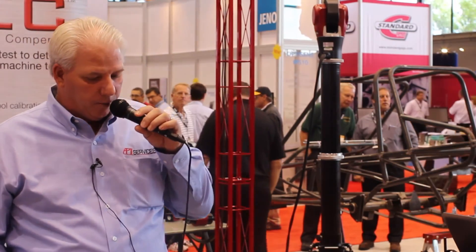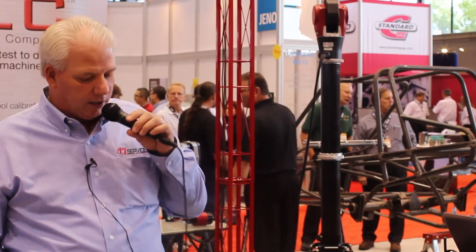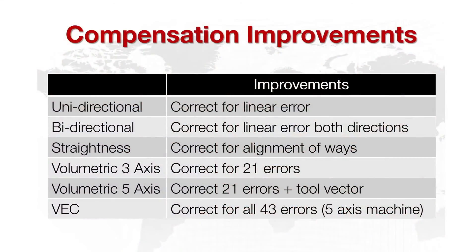To summarize the improvement you get from each calibration solution: unidirectional corrects only the linear in one direction; bidirectional corrects both directions of error; straightness corrects any misalignment of the ways. Volumetric three-axis corrects for all 21 errors; volumetric five-axis corrects for the 21 errors plus the rotary tool vector; and VEC corrects for all 43 errors.